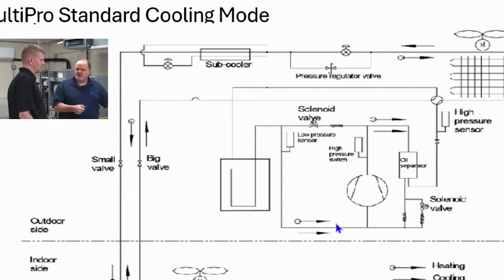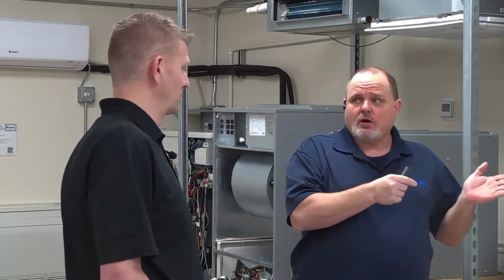The pressure drops. Yep. So right at startup, you get high head pressure, maybe not high enough to trip a high pressure switch, but then we start backing all that liquid up into our condenser. Okay? So just because you've got a restriction, and this is where I've seen a lot of guys go wrong in the years that I've been troubleshooting and dealing with HVAC equipment and refrigerant flow issues, everybody always wants to think that if I've got a restriction, I'm going to have high pressure. That's not always true. You may have high pressure to start with, but once that liquid backs up within the system, it can't move anymore, and head pressure drops.